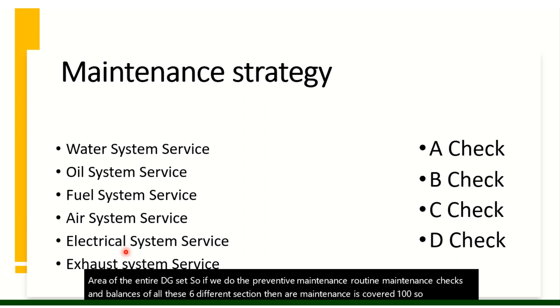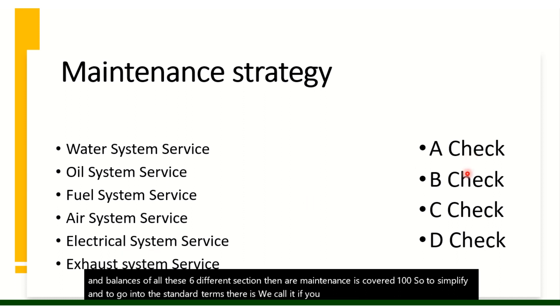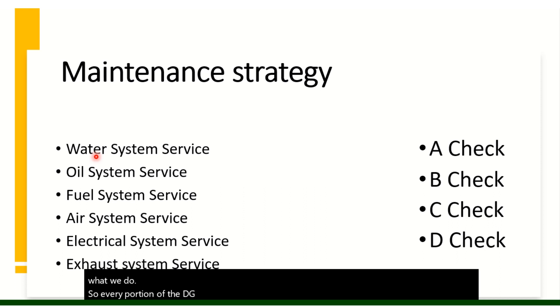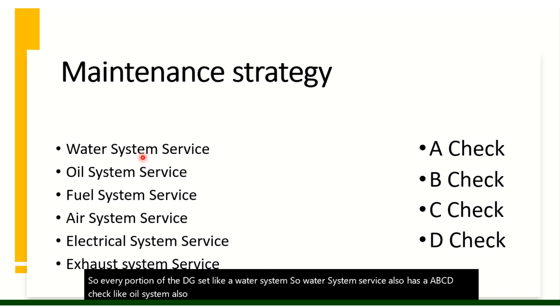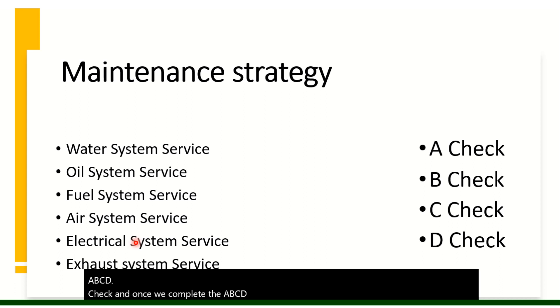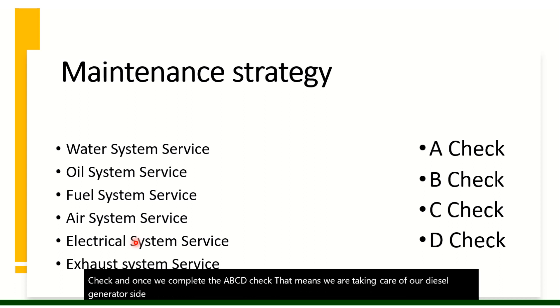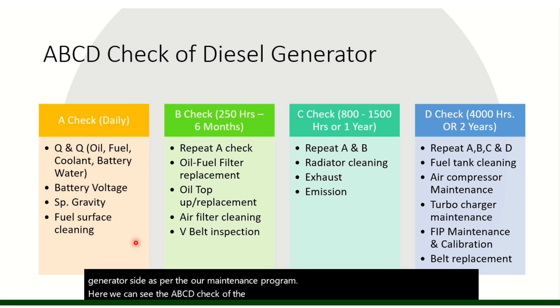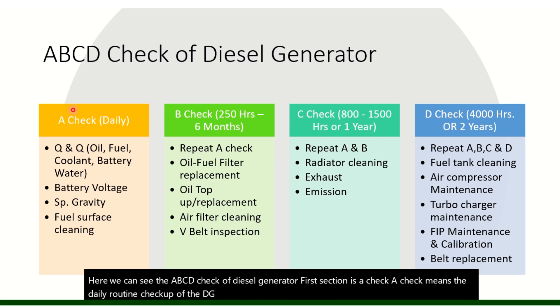To standardize these checks, we use what we call A Check, B Check, C Check, and D Check — shown on the right side. We will go into detail in subsequent modules. Each section of the DG set — water system, oil system, and so on — has its own A, B, C, D check. Once all A, B, C, D checks are completed, we have taken care of our diesel generator set as per the maintenance program. The A Check is the daily routine checkup of the DG set.